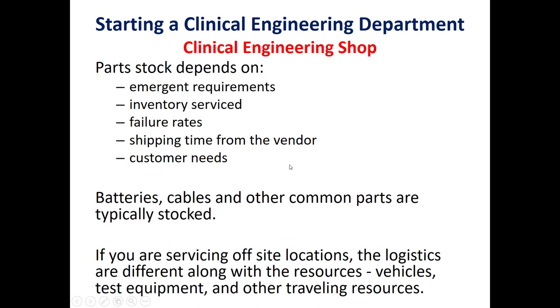The last consideration for the clinical engineering shop is the parts stock. The parts stock depends on emergent requirements, the inventory serviced, failure rates, shipping time from the vendor, and customer needs. Examples of parts that should be stored include batteries, cables, common parts, and oxygen cells. Some items like service manual kits may be needed on an annual or semi-annual basis.